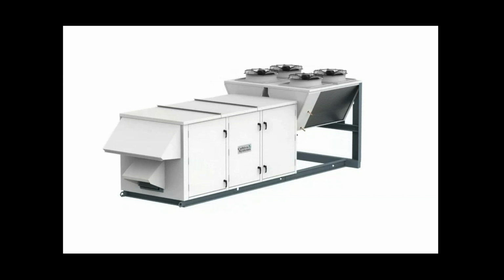All of these units can be water cooled or air cooled, and we will operate to -20. These units have to operate 365 days a year, 24 hours a day. So we've got to be able to operate in the dehumidification load all the way down to -20 degrees F.